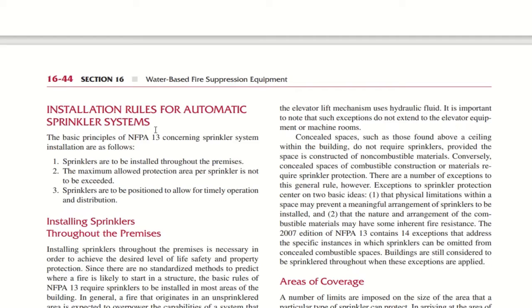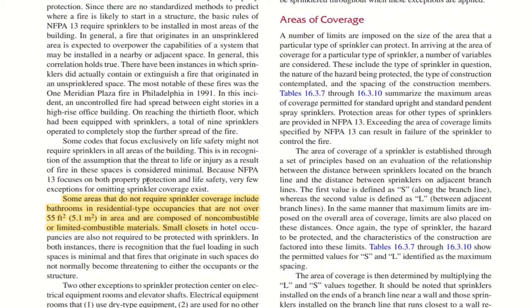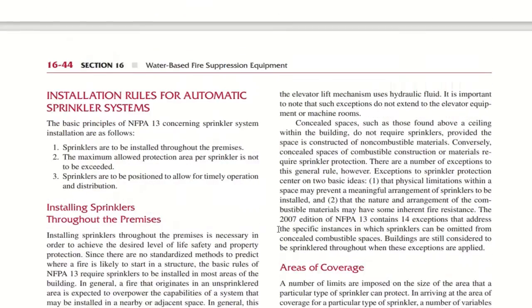And installation rules for automatic sprinkler system, they have mentioned here. There is one point, we'll just go through this. Some areas that do not require sprinkler coverage include bathrooms in residential type occupancies that are not over 5.1 square meter in area and are composed of non-combustible or limited combustible materials. Small closets in hotel occupancies are also not required to be protected with sprinklers. In both instances, there is recognition that the fuel loading in such spaces is minimal, and that fires that originate in such spaces do not normally become threatening to either the occupants or the structure. So basically they are telling that sprinklers in some areas may not be used.